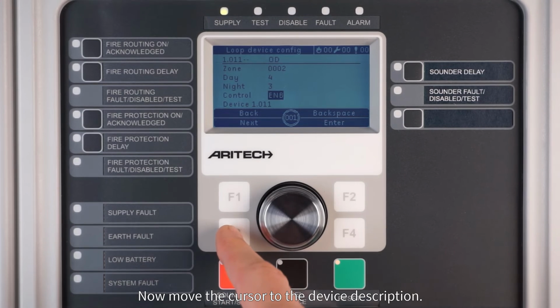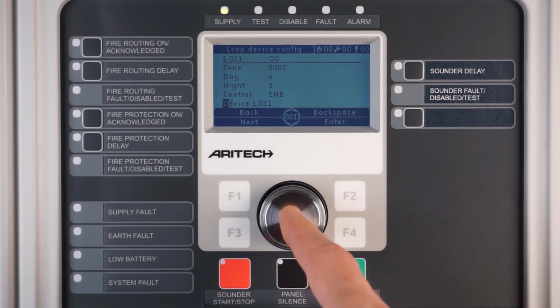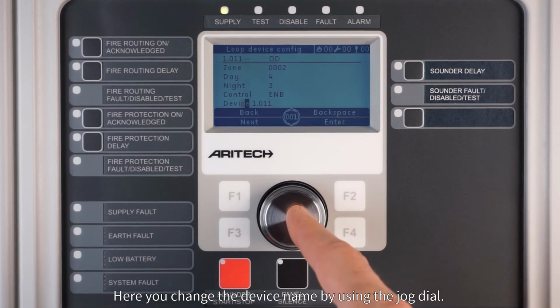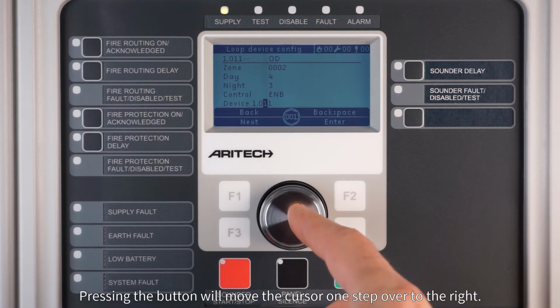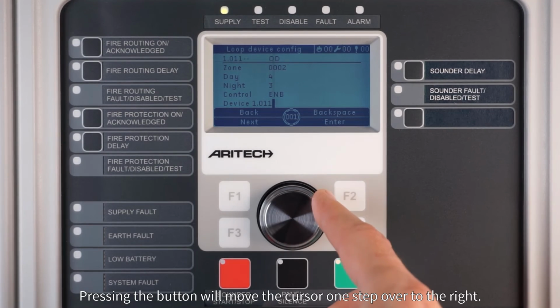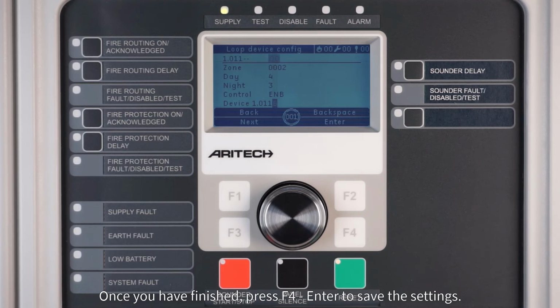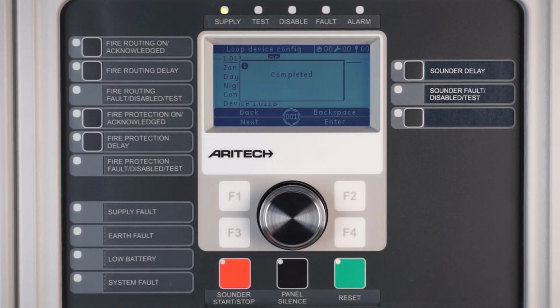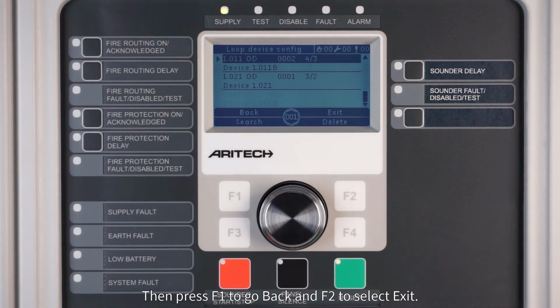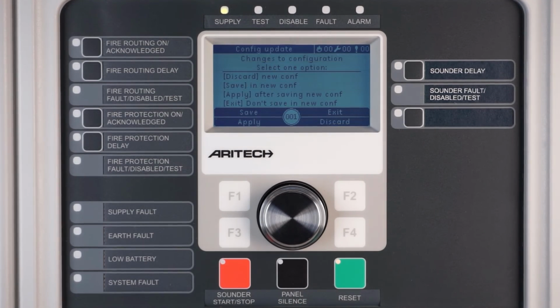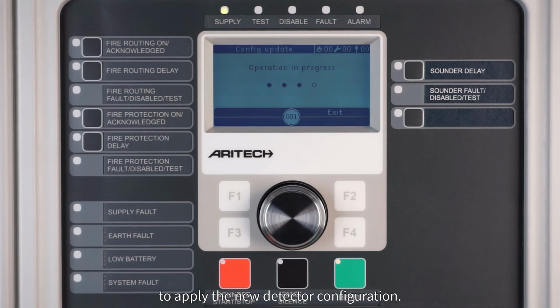Now move the cursor to the device description. Here you change the device name by using the jog dial. Pressing the button will move the cursor one step over to the right. Once you have finished, press F4 enter to save the settings. Then press F1 to go back, and F2 to select exit. To complete the process, press F3 to apply the new detector configuration.